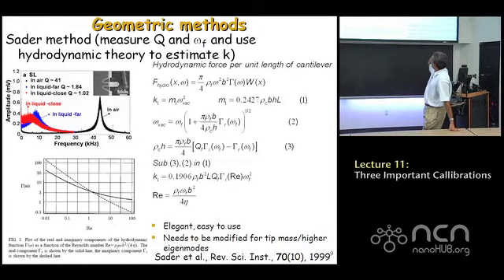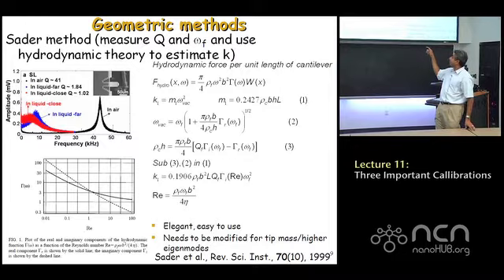So the data on the top left is the resonance curve. This is the mechanical resonances of the cantilever. The curve in black is in air, and the same cantilever, when put in water, the blue is the curve in water. So what happens, obviously, is the resonance frequency shifts completely from when you're in air and go into water. And the same thing would happen, for example, when you go from vacuum to air. So as soon as you change the medium, it changes the natural frequency of a cantilever. And we'll discuss why. The other thing that changes from air to liquid is the fact that in air the curve is very sharp, but in liquid it becomes very broad. So what that implies, of course, is that the quality factor decreases in water compared to air, and in air the quality factor decreases compared to vacuum. Okay?